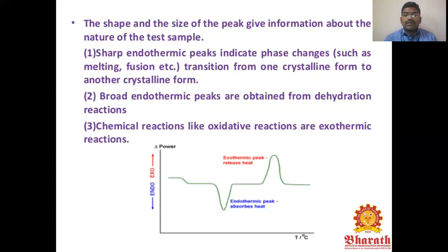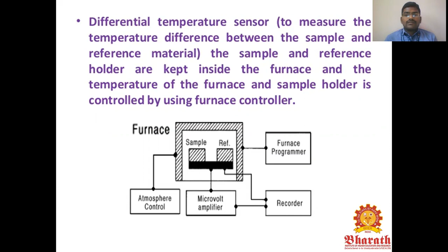The instrumentation for DTA, block diagram. The DTA apparatus consists of the following components: furnace, samples, and a heater to heat the sample, atmospheric control, low-level DC amplifier, and recording devices, the recorder. The differential temperature sensor measures the temperature difference between the sample and the reference material. The sample and reference holder are kept inside the furnace, with atmosphere control, and the sample and reference.